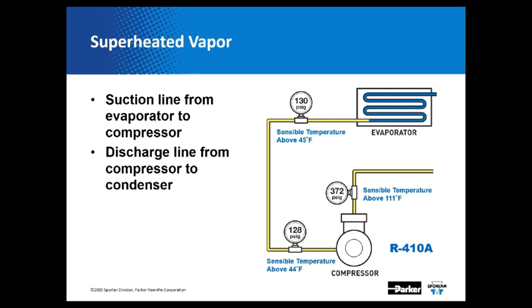Superheated vapor inside our refrigeration system serves two purposes: we want to protect our compressors, and we want to make sure we're using our evaporator coils as efficiently as possible. If we were sending liquid back from our evaporator to our compressor, we could wash out the lubricant, lose efficiency, and burn out the compressor. That's why we must have superheated vapor — it confirms we're only sending vapor back to our compressor.